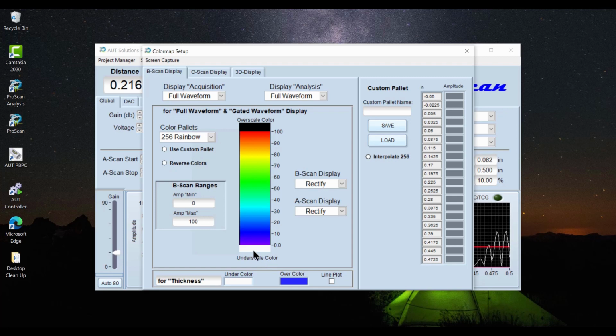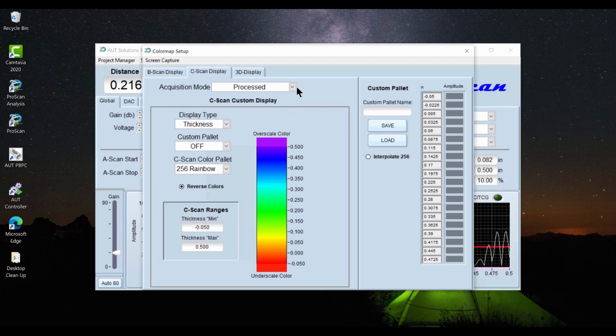So if there is no reading, the back of the screen will be white. We're going to go into C-Scan. We're going to select Processed here. And that is two different options. Process will save the B-Scan on the screen. Speed will erase it every swipe.